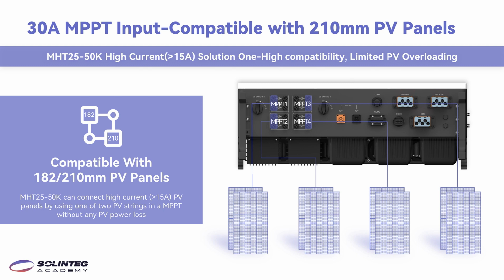On this page, in this version of inverter, there are 4 MPPT. Each MPPT has 2 PV strings. The current of each MPPT is 30 ampere. You can connect the high current PV panels by using one of the 2 PV strings in the MPPT without any power loss.